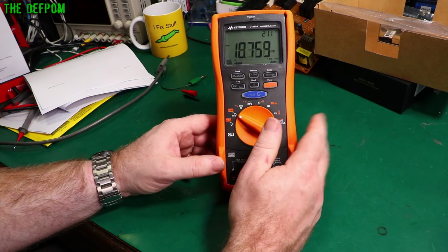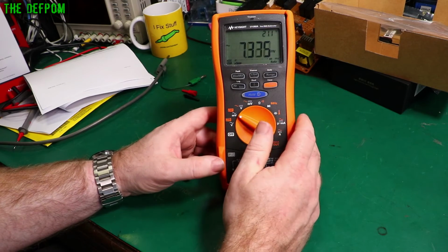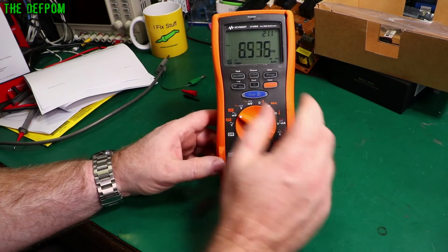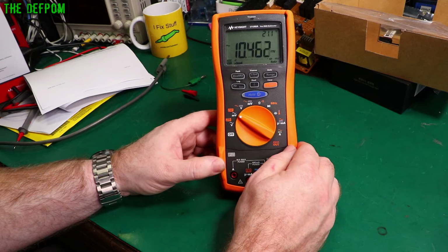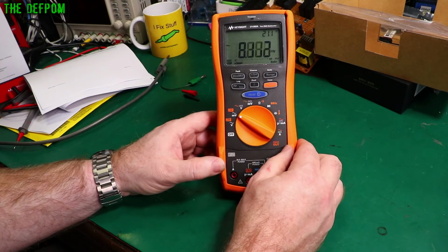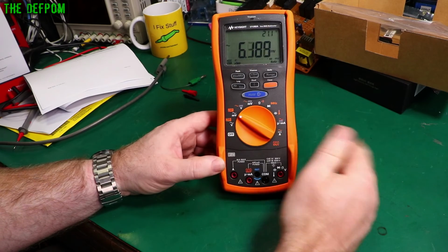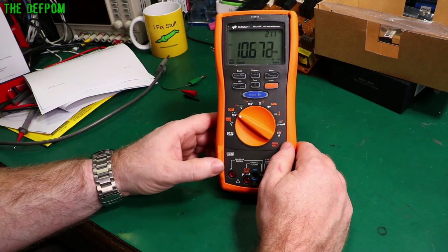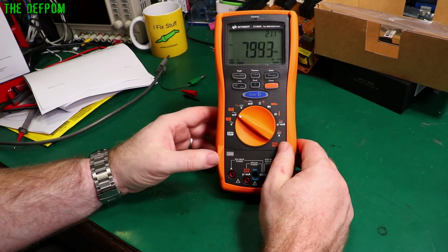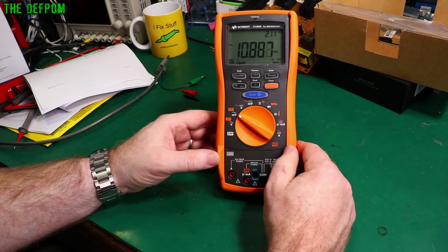There you go, it's gone off again. I personally prefer a longer backlight time, because if you're using the backlight, it's because you're trying to see the display, and in that case you probably don't care too much about battery life, you just want to see what you're doing. So I'd incline to put that value all the way up, because after 90 seconds it'll turn off. But you know, it's less likely to then happen whilst you're trying to make a reading.